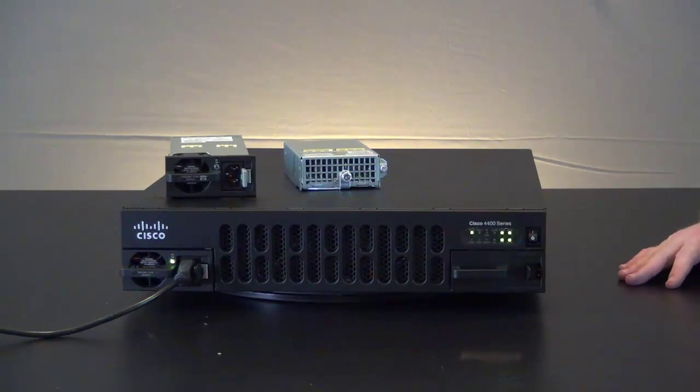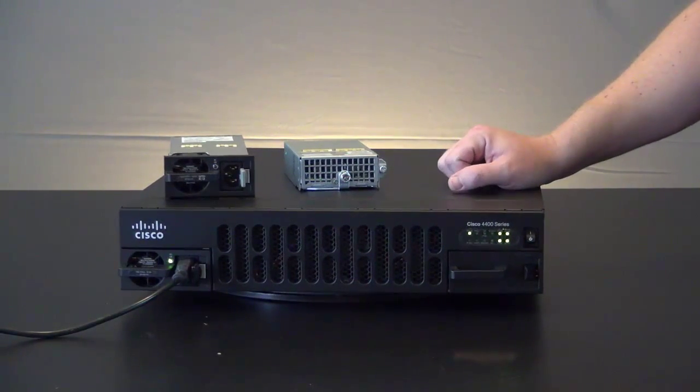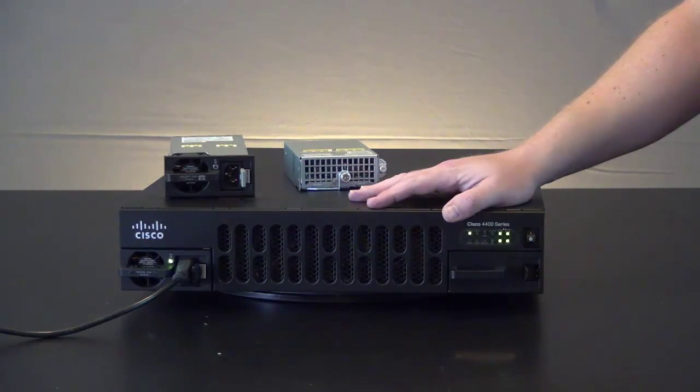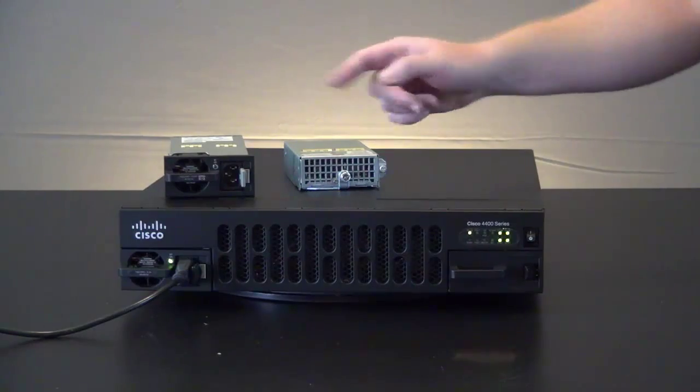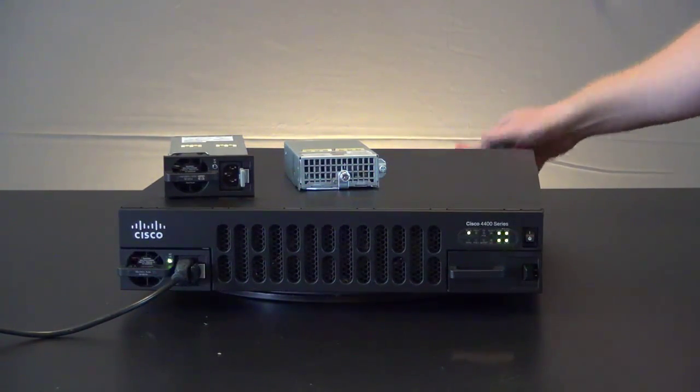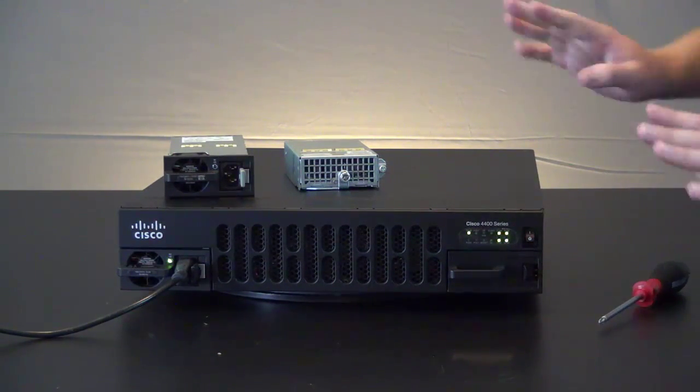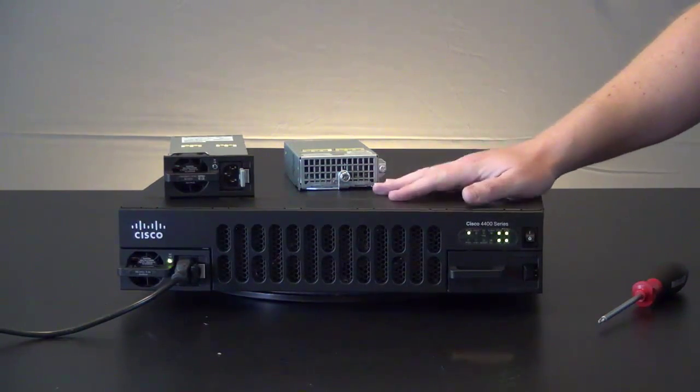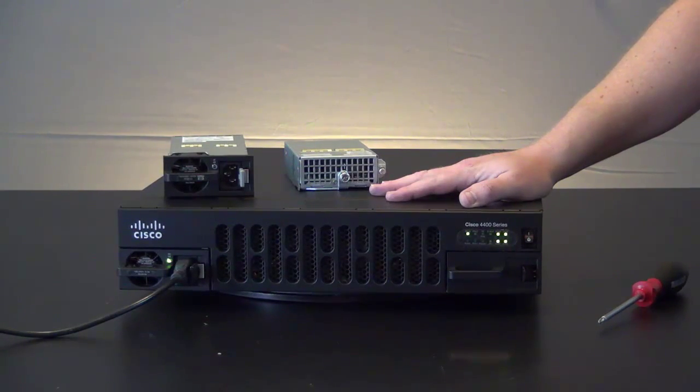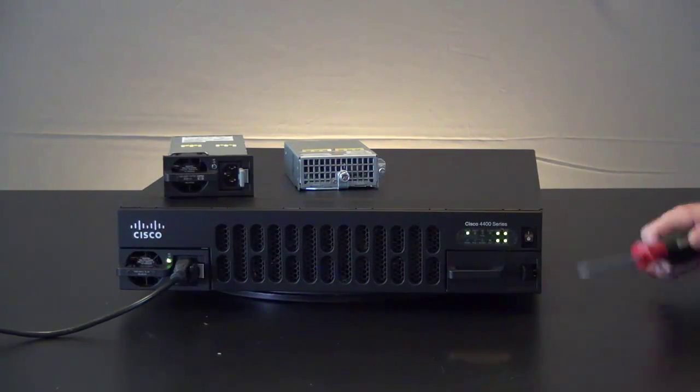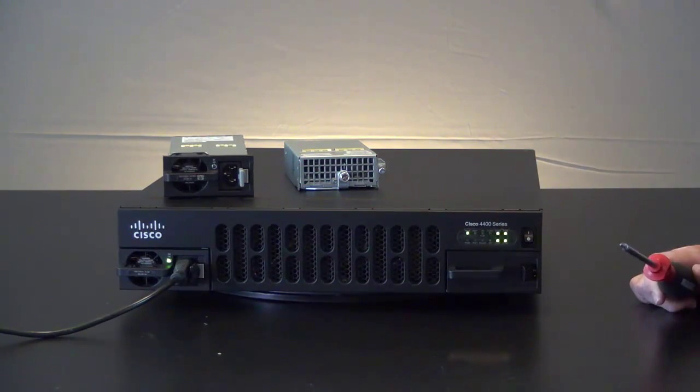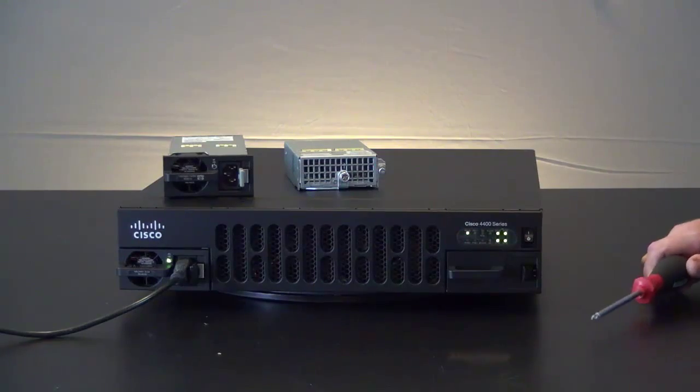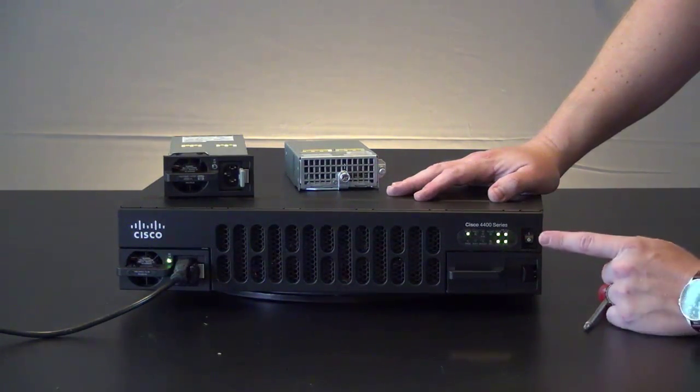All right, so we're ready to start the install. We have a running operational 4451 here. You can see all nice happy solid green lights. That's how you know the system is good. Of course, you can hear the fan noise in the system. You want to make sure that you have everything that you need before you get started. We've got our new 1000 watt power supply, our new PoE converter. And the only tool that we need is a standard number two Phillips head screwdriver. That's all you need to do this install. You can do it while the system is running, but you do want to be very, very careful. There is live voltage and live current inside of the system. For the most part, this is not stuff that you can touch with your bare fingers, but it would be very possible to take a Phillips head screwdriver and insert it into the system and cause yourself a nasty shock or certainly damage the router. Probably more importantly, damage the router or something you don't want to do. So just be careful.